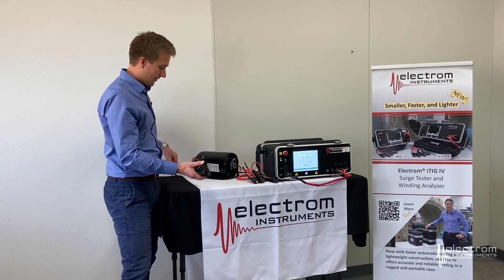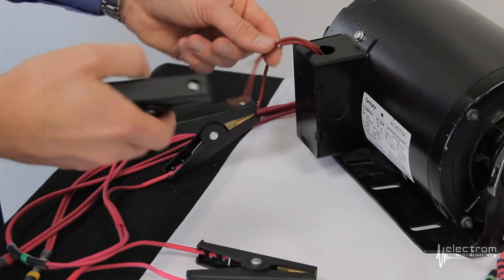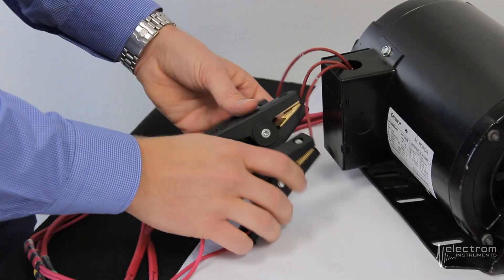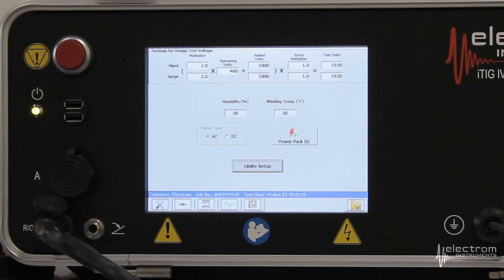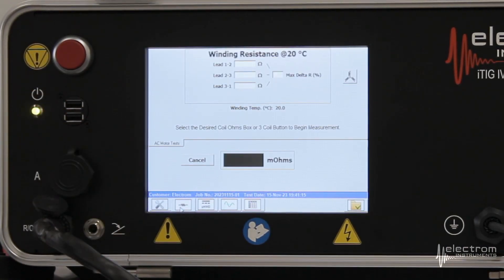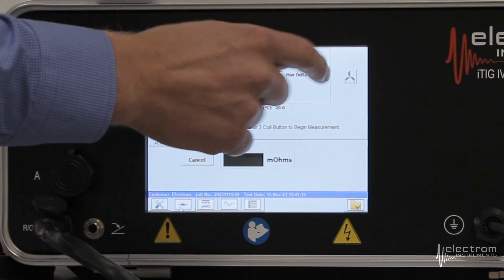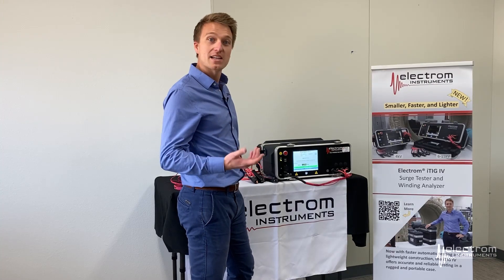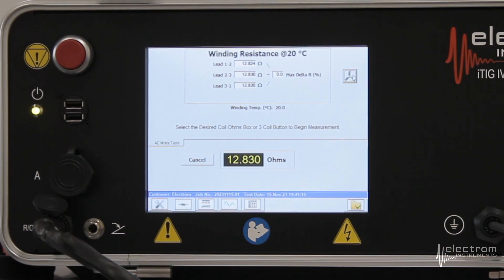We have our low voltage lead set labeled one, two, and three for phases one, two, and three. We connect clip one to phase one, clip two to phase two, and three to three. Back on the tester, we select the resistance tab — the second tab from the left. You can either do measurements manually across leads one-to-two, two-to-three, three-to-one, or click the star-coil symbol and it will run through all three phases and calculate the max delta or balance. We set our balance limit to three percent, and since we are under three percent, we have passed this first test.